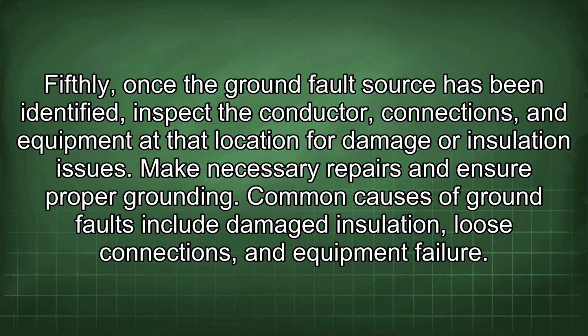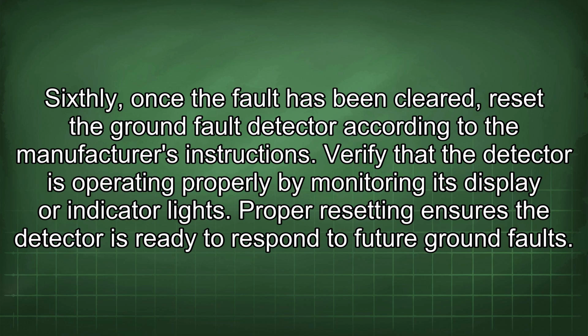Fifthly, once the ground fault source has been identified, inspect the conductor, connections, and equipment at that location for damage or insulation issues. Make necessary repairs and ensure proper grounding. Common causes of ground faults include damaged insulation, loose connections, and equipment failure. Sixthly, once the fault has been cleared, reset the ground fault detector according to the manufacturer's instructions. Verify that the detector is operating properly by monitoring its display or indicator lights. Proper resetting ensures the detector is ready to respond to future ground faults.